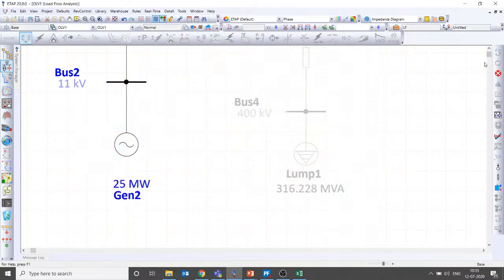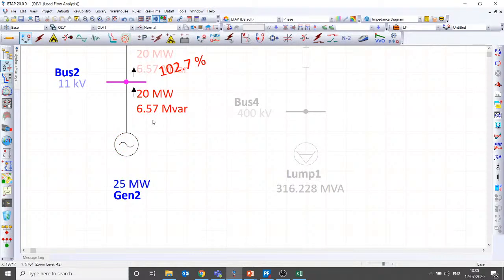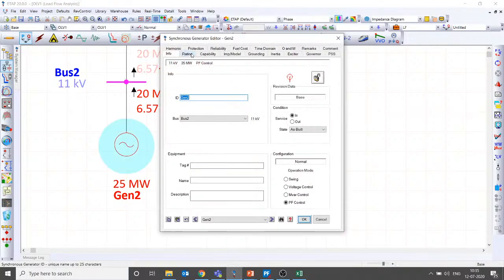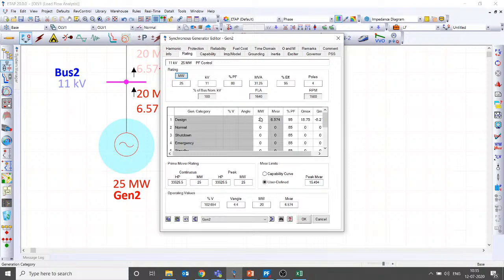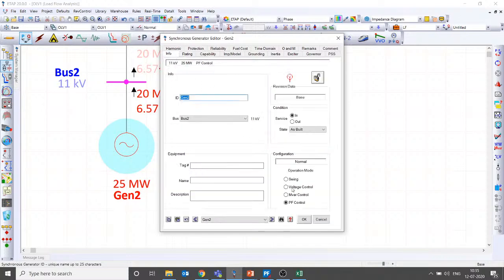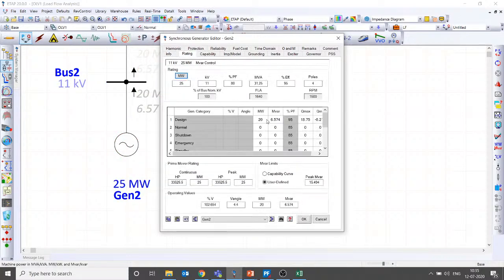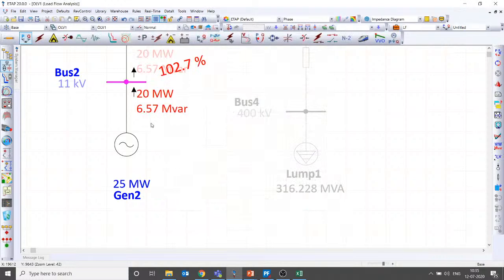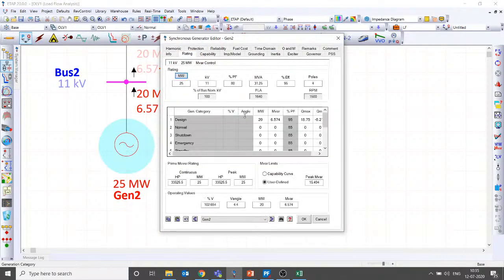So this is the power factor control mode, where the power factor remains constant. When real power changes, the reactive power also changes. But if you put it in MVR control mode, here you can see I am keeping it at 20 megawatt, 6.574 MVR. That corresponds to 0.95 power factor for 20 megawatt. Let me run. You will get the same results. It is generating 6.57. And if I increase power back to 25 megawatt, still the MVR remains the same, only the power factor is changing, right?